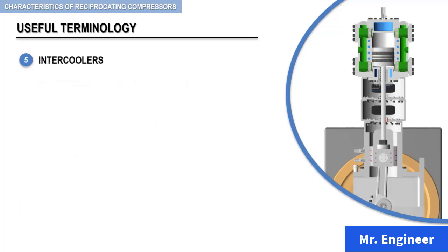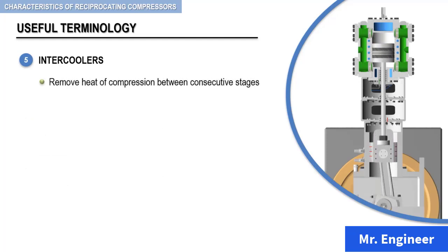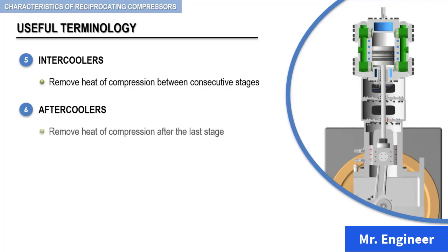Intercoolers are devices for removing the heat of compression of the gas between consecutive stages of multi-stage compressors. Aftercoolers are devices for removing the heat of compression from the gas after the last stage of compression is completed. Keep in mind, aftercoolers are one of the most effective means of removing the major amount of moisture from the air provided they have the capability of cooling the air down to less than 100 degrees Fahrenheit.